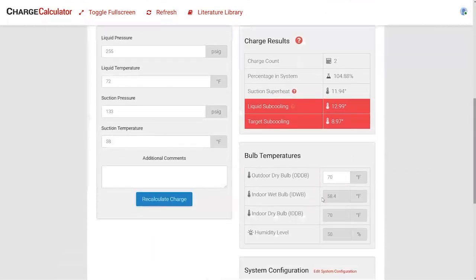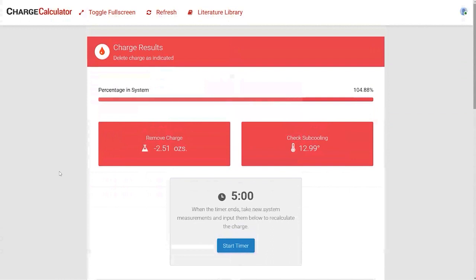The charge calculator is really best used as a commissioning tool. It won't necessarily help troubleshoot a refrigerant restriction. On a new startup — with everything free of restriction — use this tool to ensure the system is properly charged for either a TXV-driven system checked by subcooling, or a piston system checked by superheat. For a piston system it'll give you a target superheat number instead of a target subcooling number.